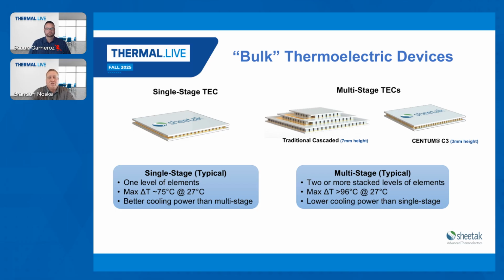Multi-staging is adding different layers of elements across the devices, so you could go with 2 stages, 3 stages, or 4 stages. The reason that you put the stages together is primarily so that you can increase that delta T across the device. So whereas a single stage has 75 delta T max, a 2 stage may have 97, a 3 stage may have 100, 110. The more stages you add, the more delta T, but the lower the cooling power that you get. There are different ways of doing the multi-staging. In some cases, you add an intermediate ceramic and add different stacks of elements. There are other ways, like the Centum C3 product line, where we eliminate the intermediate ceramic and directly stack the elements on top of each other for more compact sizes. So there are different ways of implementing single and multi-stage.